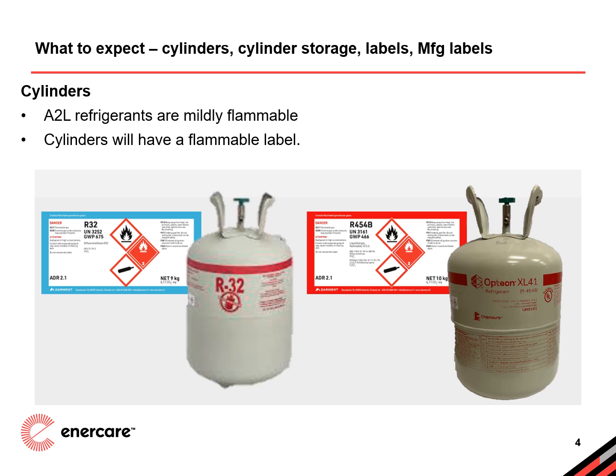As we work more with A2L refrigerants, there are some key safety considerations to keep in mind. First, let's break down the acronym A2L. The A indicates that these refrigerants are non-toxic, while the 2L classification refers to their lower flammability. This is different from the traditional refrigerants many of us are used to, which are typically non-flammable.